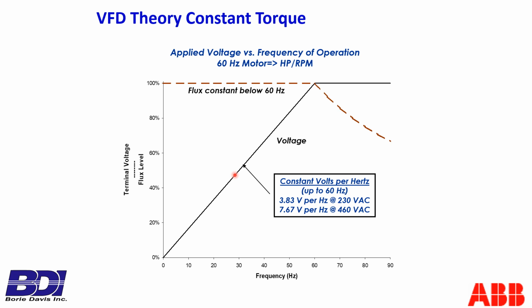So you only did half the work, but as you can see, if this is also the power vertically shown, only half of the power, 50% of the power was required. 100% is required at 60 hertz, 50 at 50% speed, 30 hertz, only 2.5 horsepower will be required. Now, in some applications, there is a desire to go above 60 hertz.